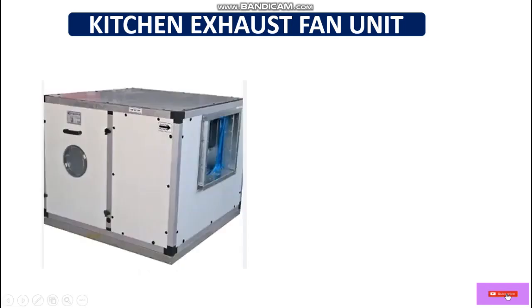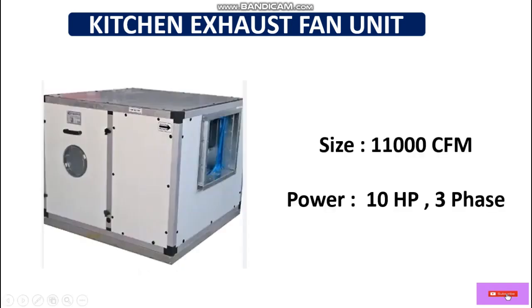So here we are going to calculate the contactor size for a kitchen exhaust unit star delta starter. This is the kitchen exhaust fan unit. Its size is 11,000 CFM and power consumption is 10 HP.